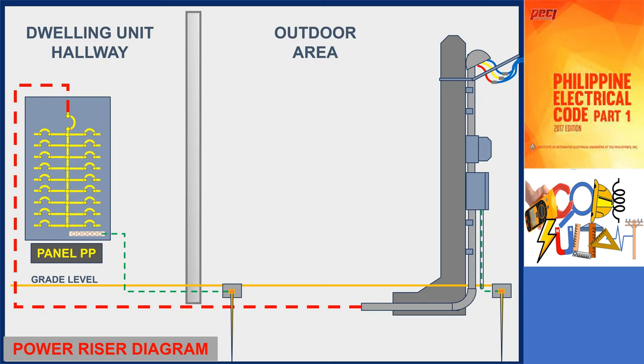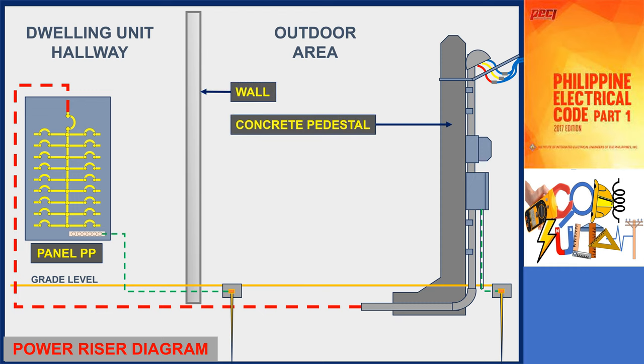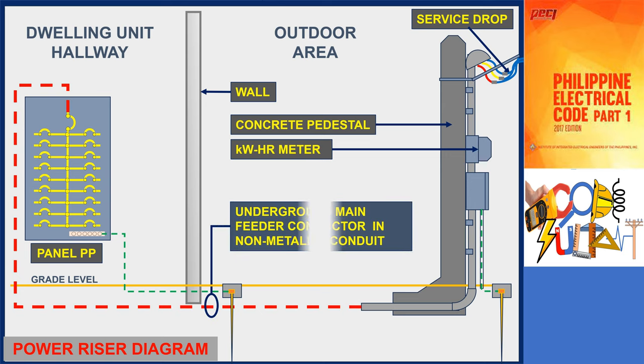For our project, the service entrance will be mounted in a concrete pedestal, and the main feeder conductors shall be installed underground in non-metallic conduit. The figure shown is the power riser diagram for the project. A concrete pedestal is used to mount the service entrance and other accessories required by the local electrical utilities such as kWh meter, service head, etc. In this video, we will determine the size of the main feeder conductors, main overcurrent protective device of the dwelling unit panel, and the service and service equipment rating.